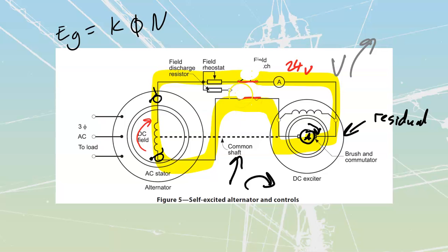If I want to open the field switch, the first thing that happens as I'm starting to open it is that I reestablish that very first connection across the field discharge resistors. This connection gets remade here again, which means now I'm going to have current delivered from here going through there. That's going to be fine.